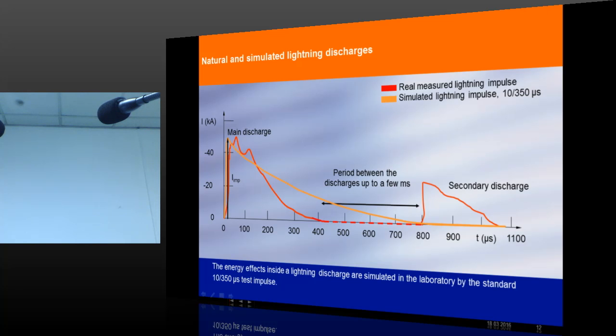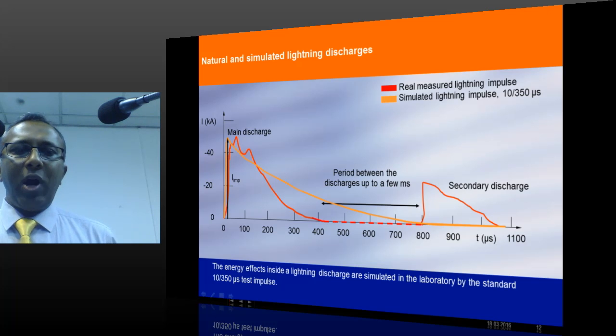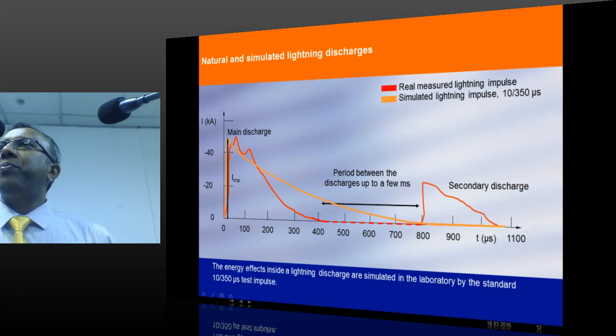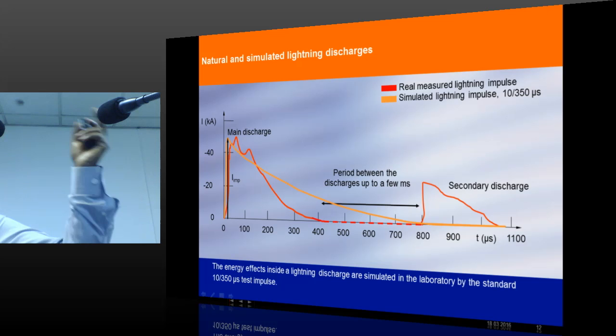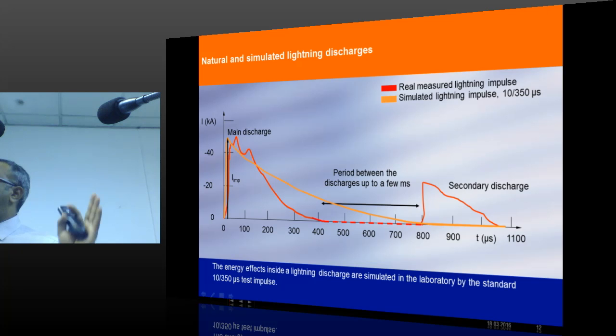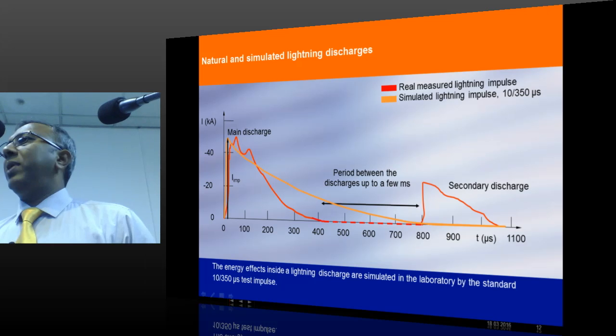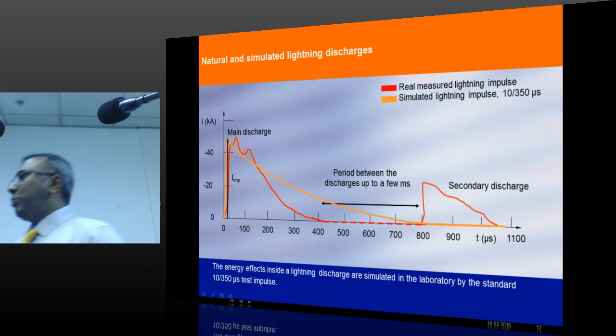With respect to time, the energy equivalence of a lightning strike is calculated as 10 by 350 microseconds. 10 by 350 microseconds means the lightning current goes from 0 to peak and comes to half value in 350 microseconds. This orange line. It doesn't mean that lightning is always following 10 by 350. No. Lightning will be maybe 100 by 1000 or whatever it is. That is not the point. The point is to protect the building. Once we design a lightning protection system for the building, we need components like conductors, connectors and so on. How these components are tested is more important. The equivalent energy wave shape given in the standard is 10 by 350 microseconds. You know, this particular part, this 10 by 350, is important for you, especially when you buy components.